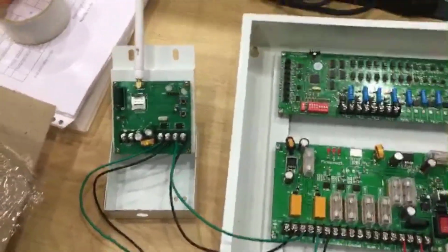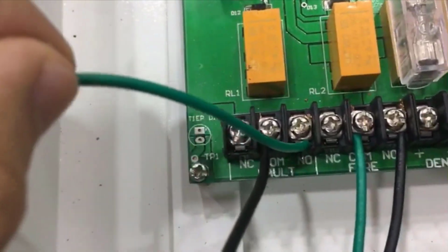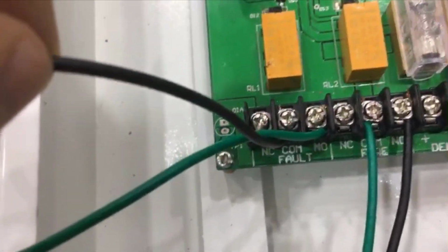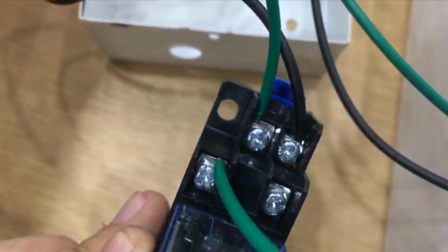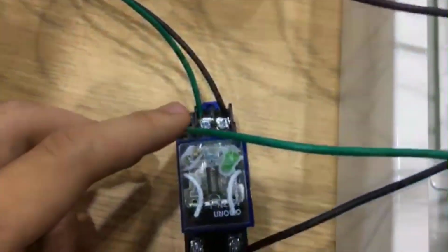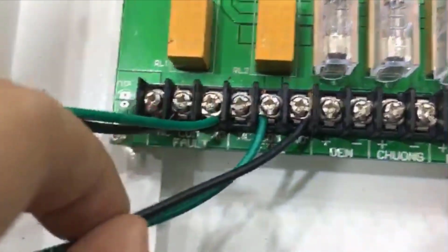In case you are using an RST cabinet, connect the fault port on the FS-001 device to the NO and COM contacts on the fault port of the RST. Connect the fire port on the FS-001 device to the contacts 13 and 14 of the relay. Then, connect the wires from the contacts 5 and 9, or 8 and 12, on the relay to the NO and COM contacts of the fire port of the RST.